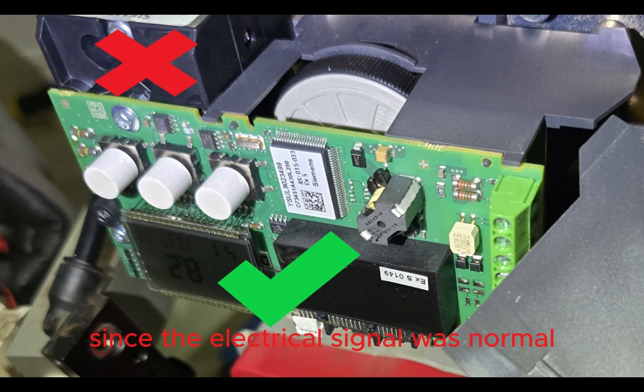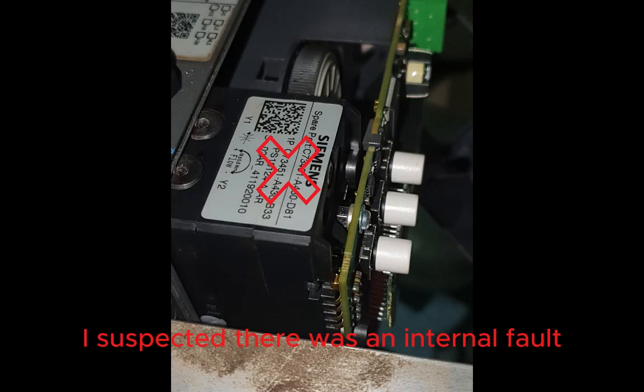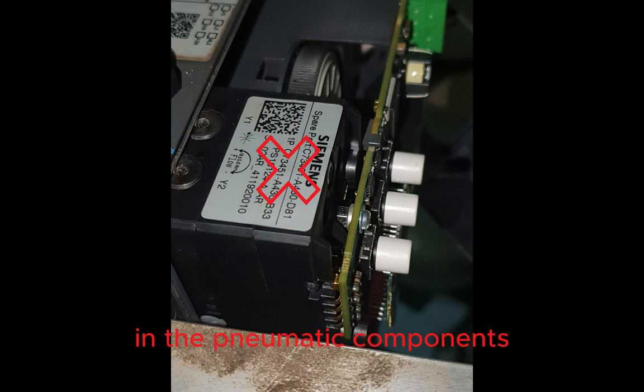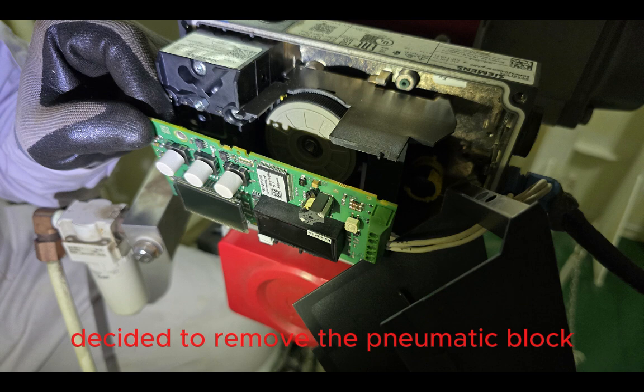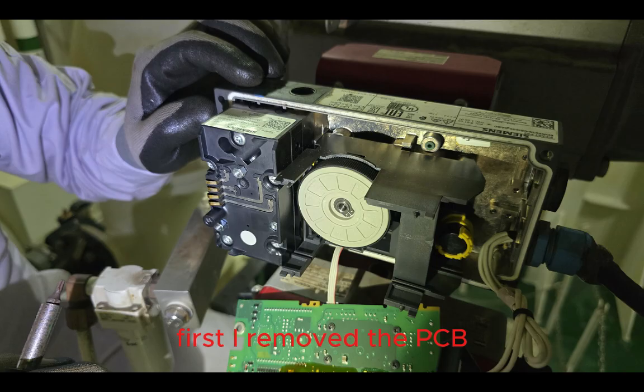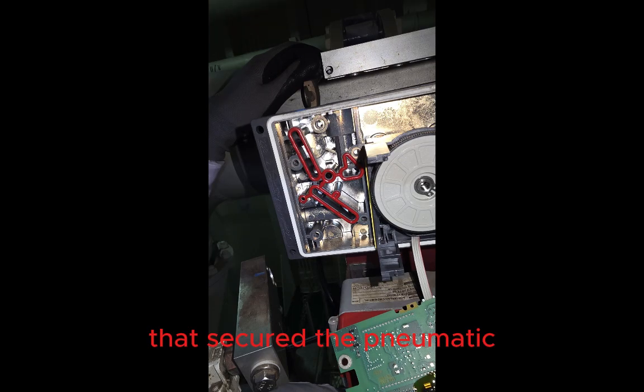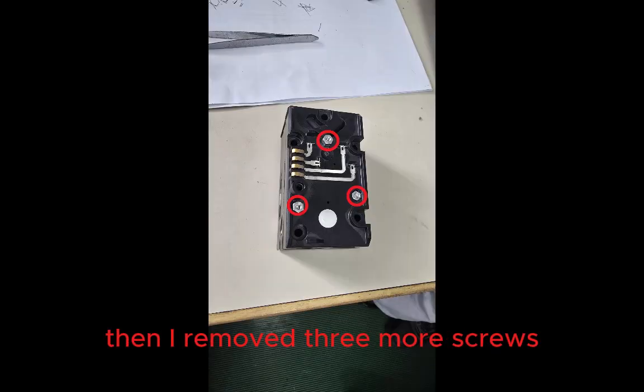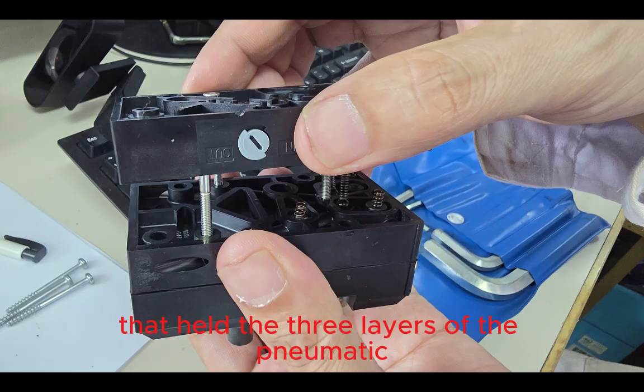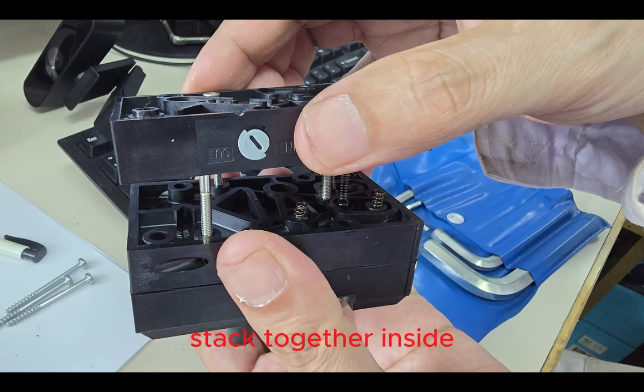Since the electrical signal was normal, I suspected there was an internal fault in the pneumatic components. So I decided to remove the pneumatic block from the positioner and inspect it. First, I removed the PCB which was covering the pneumatic block by taking out 2 screws. Next, I removed 5 screws that secured the pneumatic block to the positioner casing. Then, I removed 3 more screws that held the 3 layers of the pneumatic stack together.